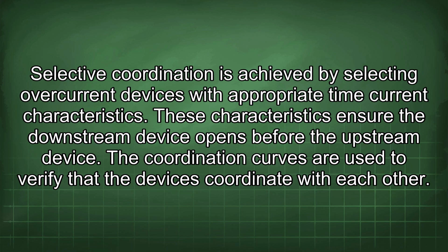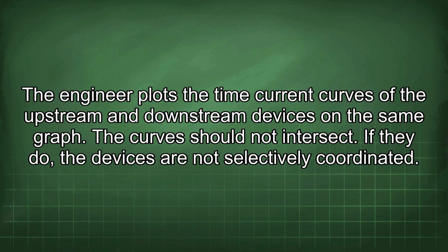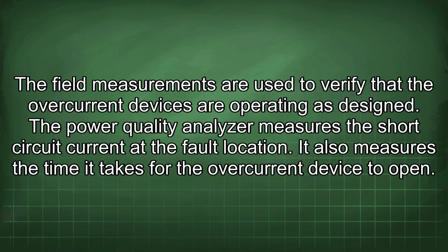The coordination curves are used to verify that the devices coordinate with each other. The engineer plots the time current curves of the upstream and downstream devices on the same graph. The curves should not intersect. If they do, the devices are not selectively coordinated. The field measurements are used to verify that the overcurrent devices are operating as designed.